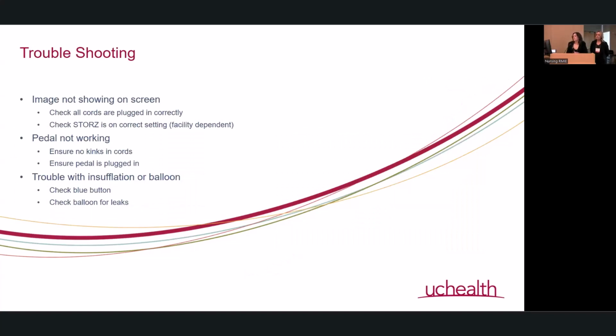Troubleshooting for the EUS. Sometimes the image is not showing on the screen. Again, make sure everything's plugged in. Check the processor is on the correct setting. And then if the pedal is not working, just make sure there are no kinks in the cord and that the pedal is also plugged in. If you can't tell, we have had issues with things being plugged in before. Trouble with insufflation or balloon, like I said earlier, that can happen pretty frequently and very important just to check before you get started.